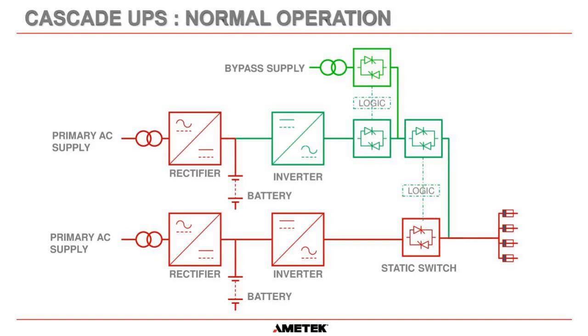So once again, you will have UPS backup in both of those situations. And just like the parallel redundant system, you will have bypass supply if necessary, if both UPSs fail. The issue with this design compared to a parallel redundant UPS is that the points of failure become more apparent in a cascade UPS, because this static switch here and this static switch here are the only two that control power to your load circuits. This static switch for the bypass is behind this one.